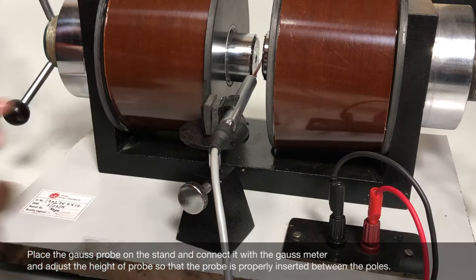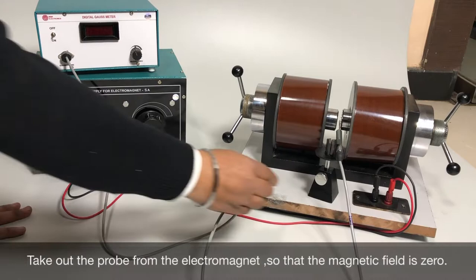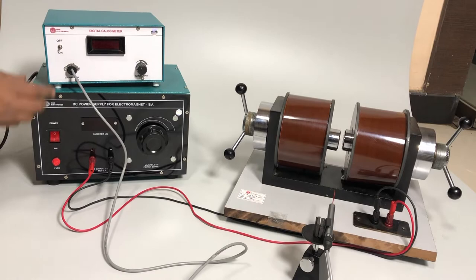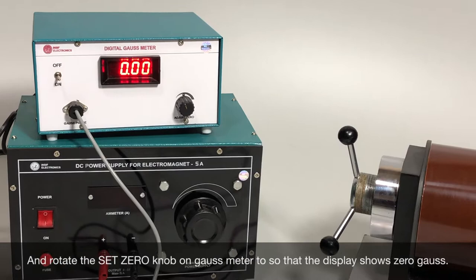Take out the probe from the electromagnet so that the magnetic field is zero. Now switch on the digital gauss meter and rotate the set zero knob on gauss meter so that the display shows zero gauss.